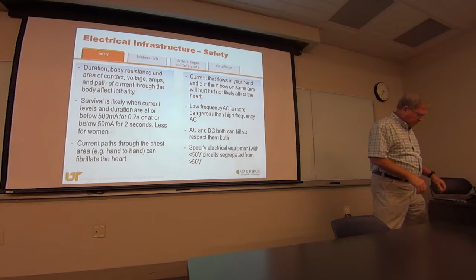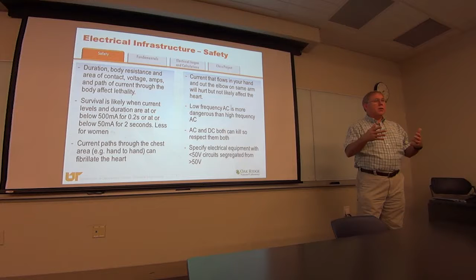Electrical equipment - maybe you'll get into this - you buy a piece of gear with some 50 volt, or say 24 volt control stuff. You can touch the 24 volt stuff, but they'll stick it right in the middle of a 480 volt cabinet. We want to ask them to separate the stuff, and we get manufacturers to do that for us, to segregate the low voltage over here so we can work on the controls and PC boards. Look for that kind of thing, because manufacturers are doing it more and more now, but they used to just mix it up because everybody worked everything hot - nobody cared.